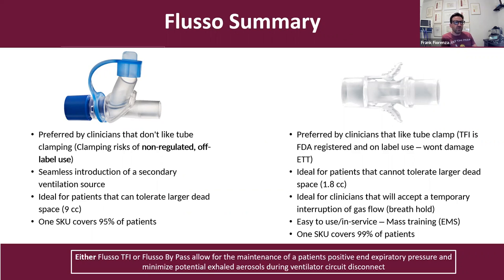So if you look at Flusso bypass, clinicians that use it don't like tube clamping. Tube clamping is taking a pair of surgical forceps to the neck of the endotracheal tube, squishing the tube, occluding it, trying to keep the PEEP by that method. But that could damage the tube, it's not regulated, it's not FDA approved, and it's off-label use by the manufacturer of the endotracheal tube.